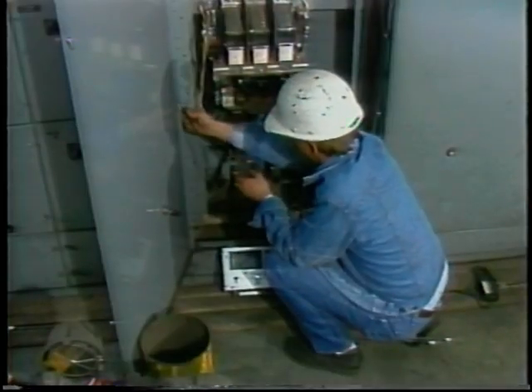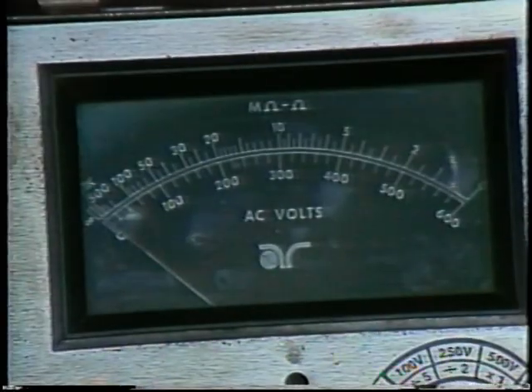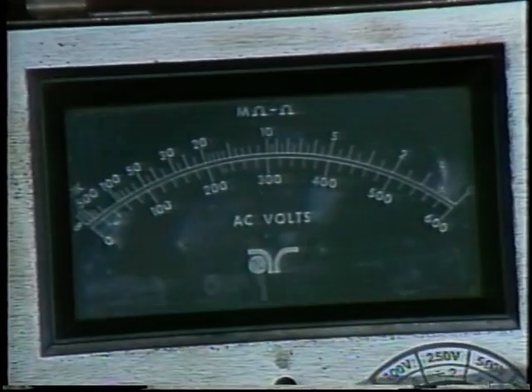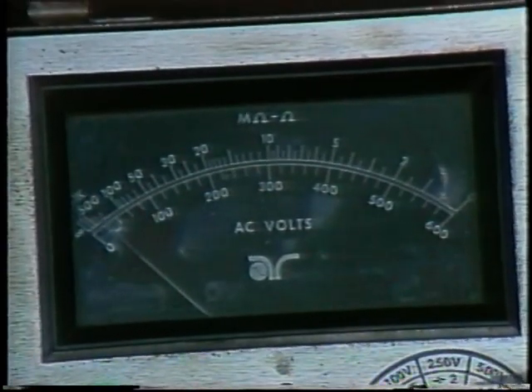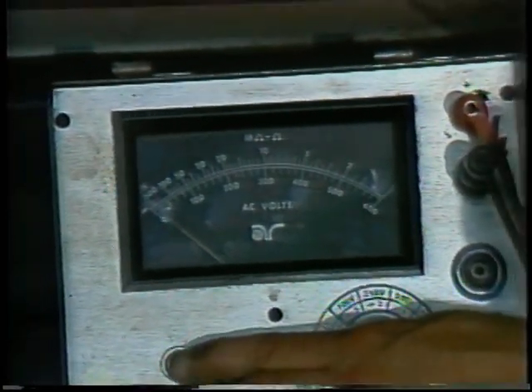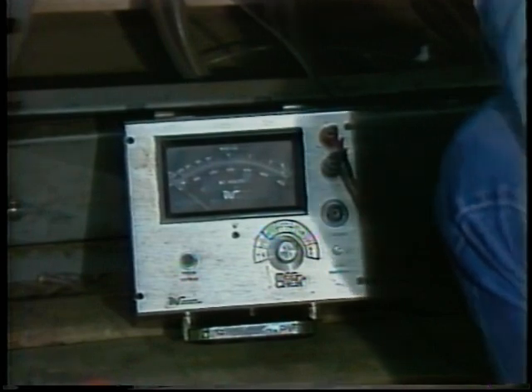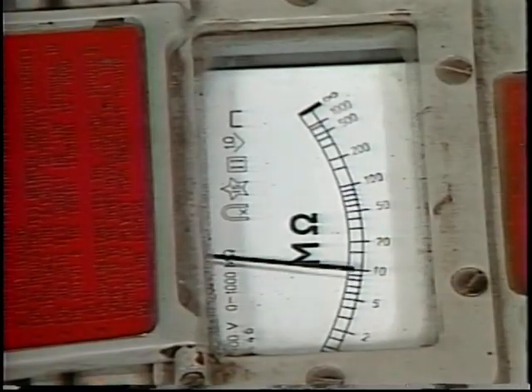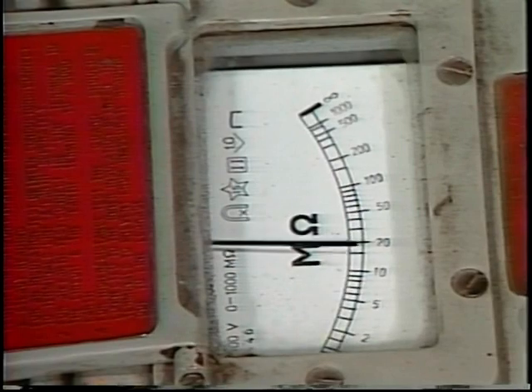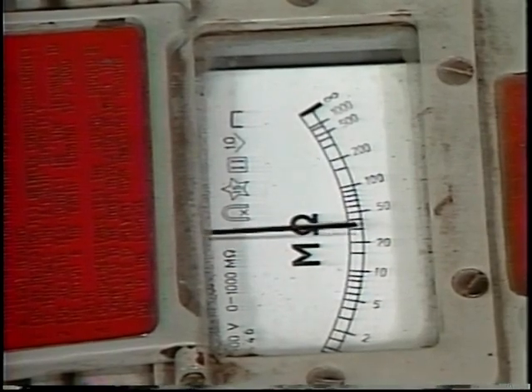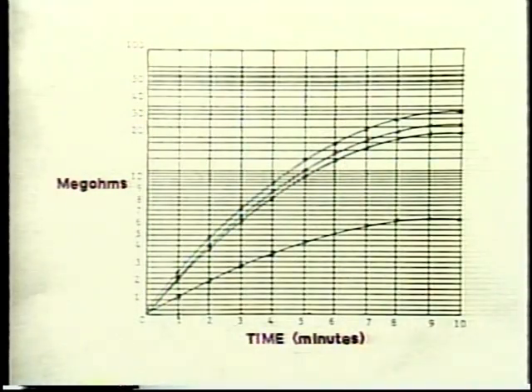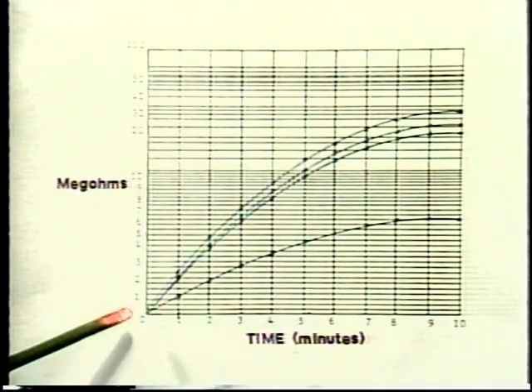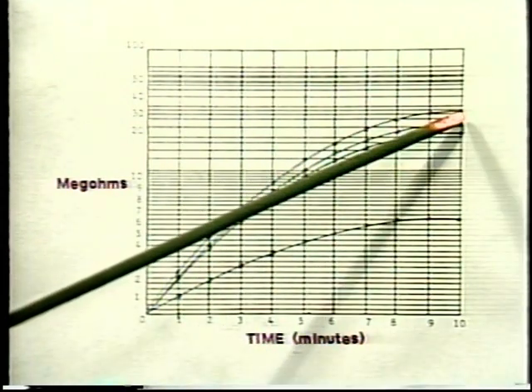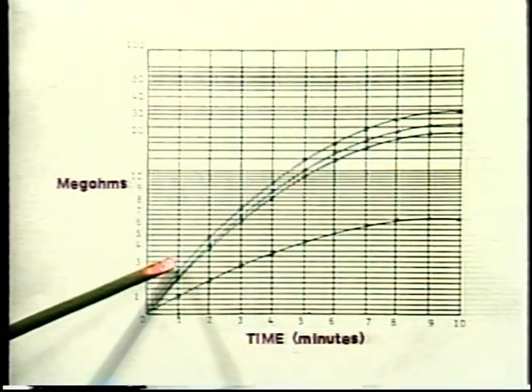Second, you may need to interpret the reading. Usually, a good motor will quickly produce a very high reading of at least several hundred megohms or even infinity. A much lower reading, however, does not necessarily mean a motor problem. High temperatures and humidities will reduce the reading significantly. Also, the insulation in some motors needs time to charge up, like a capacitor. Some test procedures specify keeping the voltage applied for as much as 10 minutes. If the reading keeps rising and is at least twice as high at 10 minutes as it was at 1 minute, the insulation is probably okay.